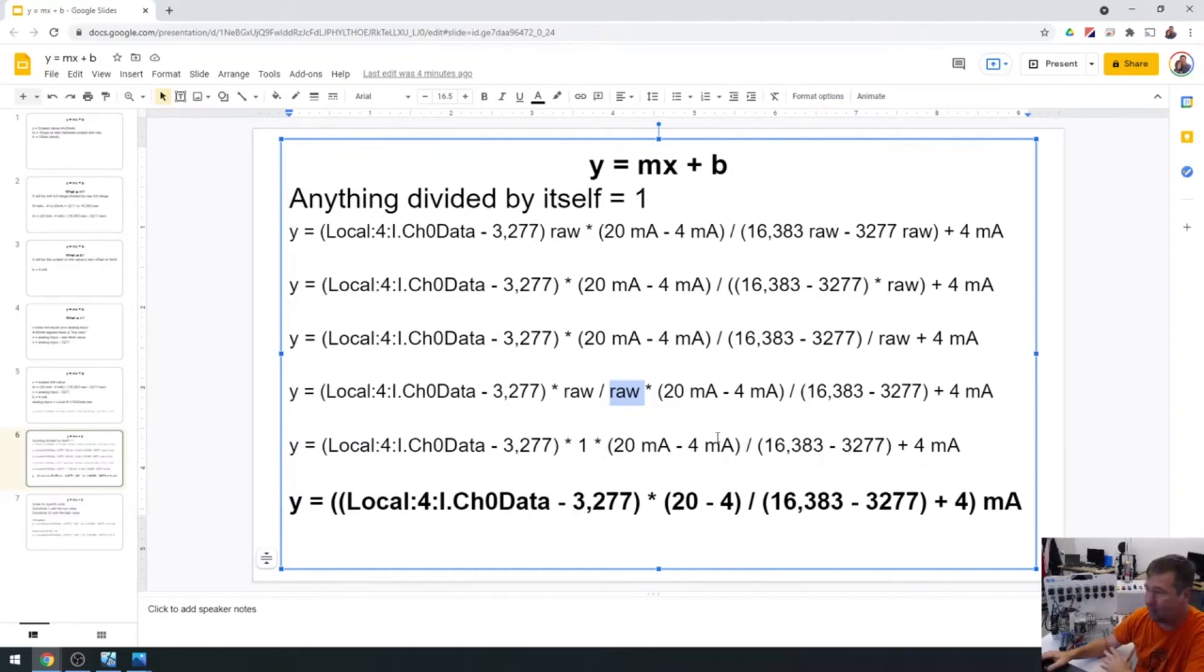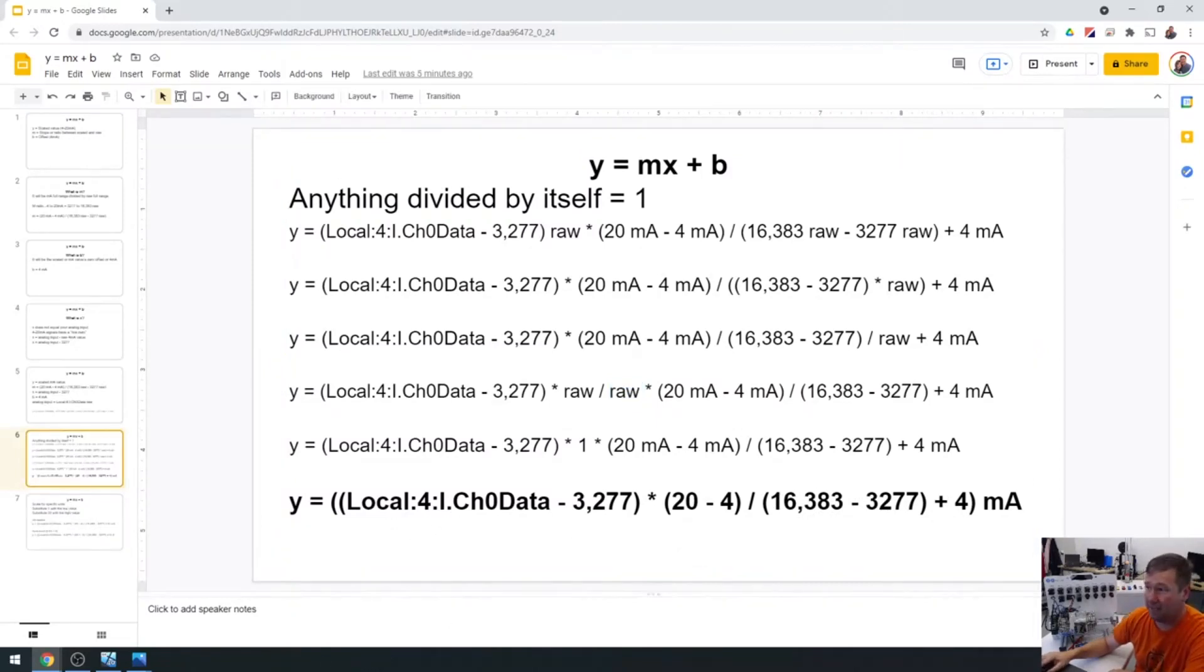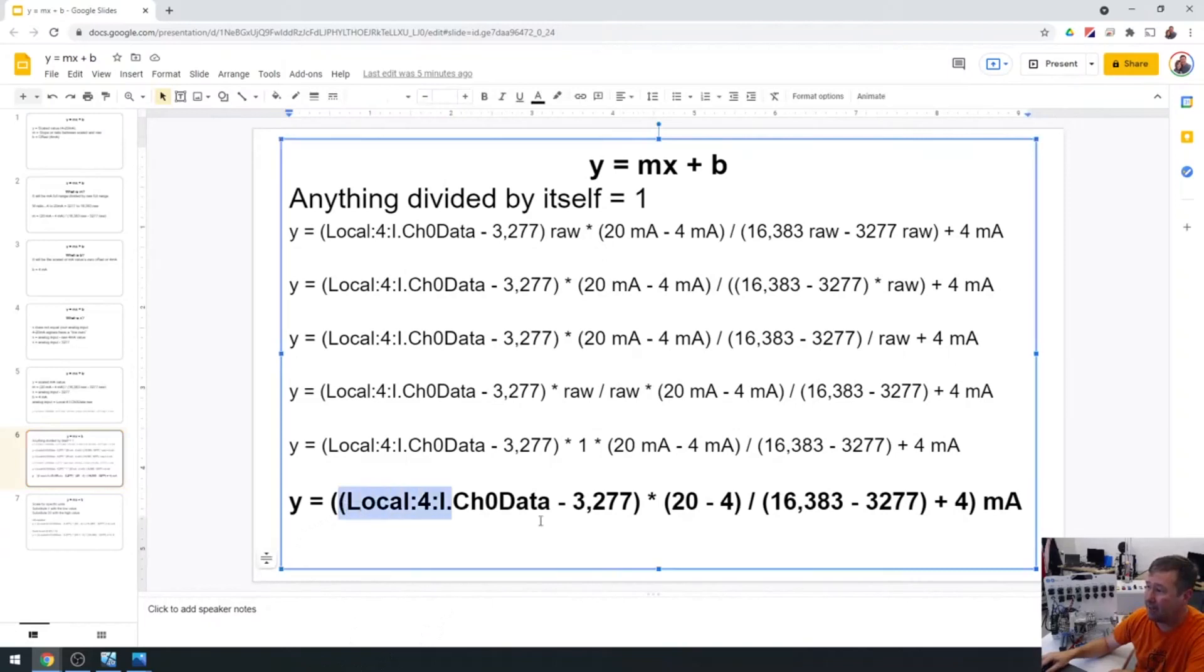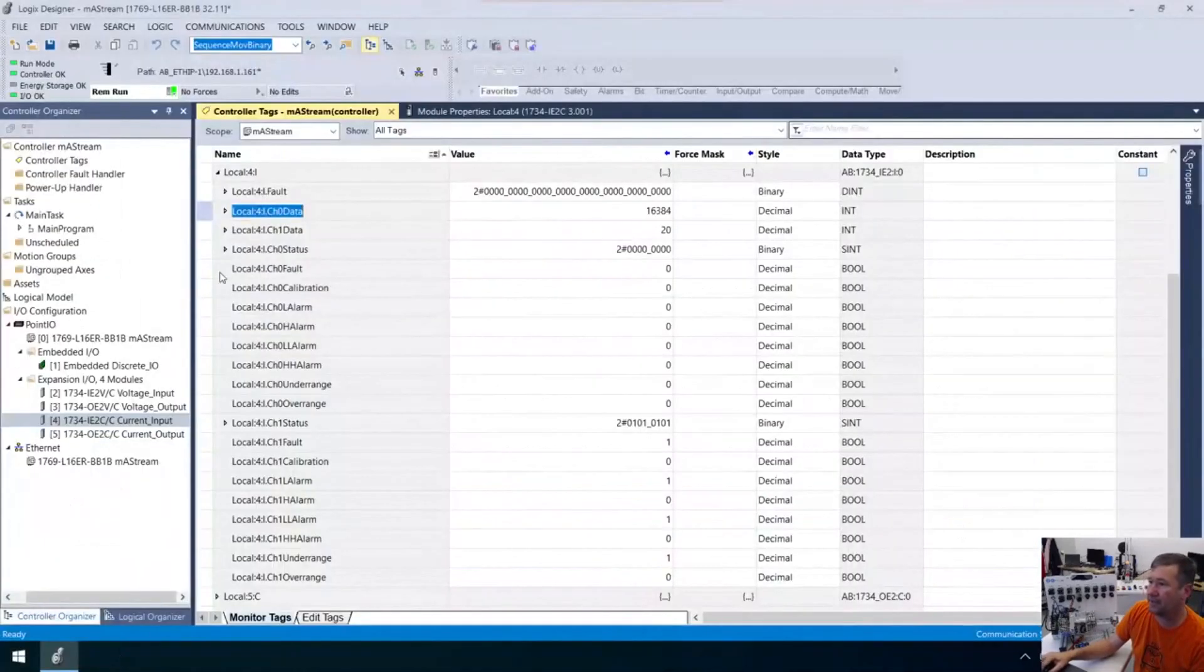Somebody put it in chat if you really want me to go deeper into this because I kind of threw this slide in just in case somebody really questioned or really wanted to know why. Hey, Daryl, glad you could make it on. But okay. In the end, here's our equation. So local colon four colon I channel zero data minus 3277 times 20 minus four divided by 16,383 minus 3277 plus four. That's going to be our four to 20 milliamp value. Now that's a lot of numbers. And we did not come here to do math. We came in here to figure out how to do analog inputs. So what can we do with that? I'm going to highlight this now and I'm going to copy it.